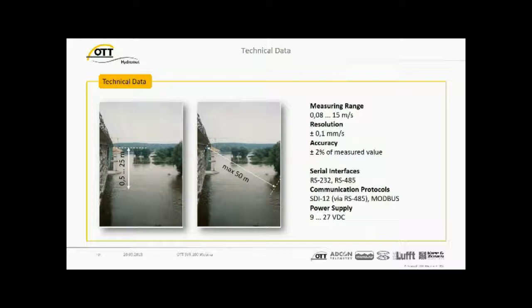Just an additional remark to this. The serial interface is, as you see here, RS-232 and RS-485. We don't have a physical SDI-12 interface. That means we can't wake the sensor up and say, okay, start your measurement, give me the values back, and then go into sleep mode. This is not possible here.